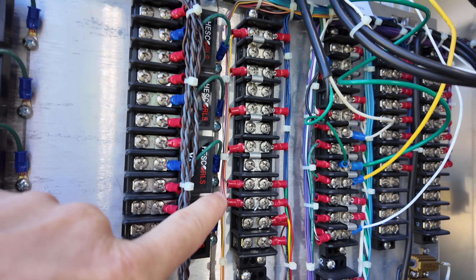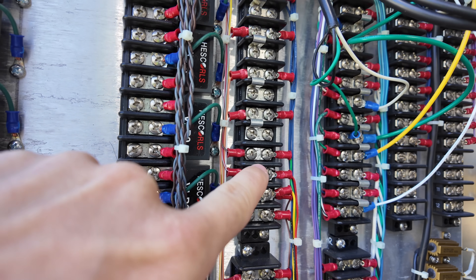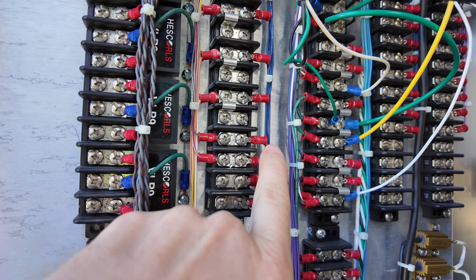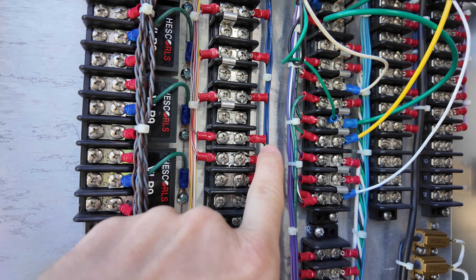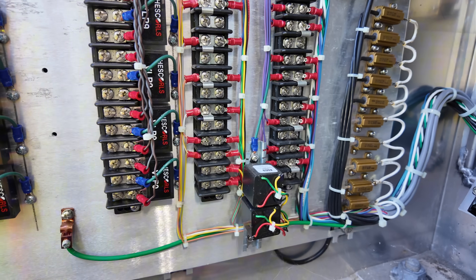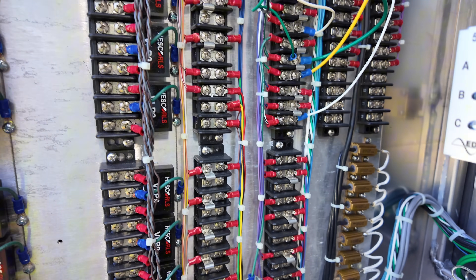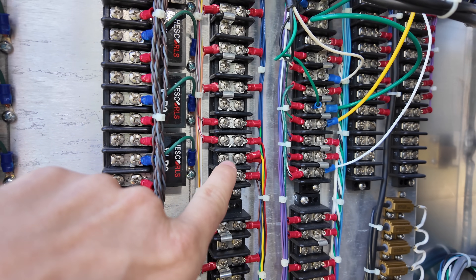Now the real magic starts happening. On the side panel on the L-block at position 9, cable A is sitting right there, and you can see another cable coming out of that terminal block. This wire jumps down into a surge protector, because we don't want to damage anything inside the cabinet if a surge happens on that push button.